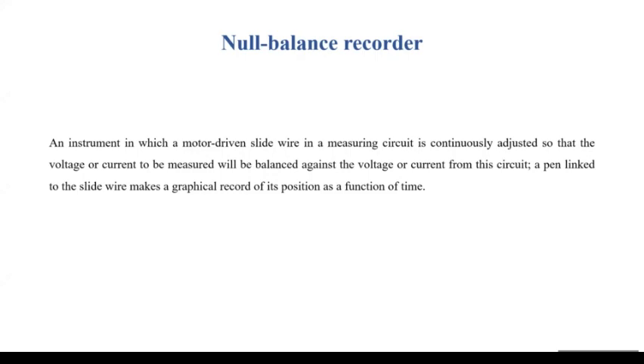In the system, the input signal under measurement is compared with the reference voltage produced by a feedback element which is accurately calibrated with respect to a mechanical position on an output display scale. The detector or servo amplifier senses the difference between the unknown and the reference voltages and actuates a motor which positions an indicator on the output display scale for a zero error or null voltage condition between the unknown and reference voltages.